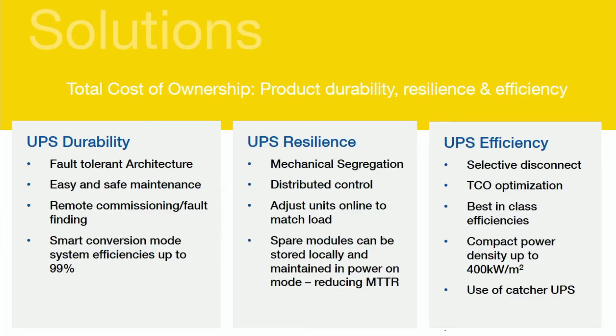Yeah, so this is where instead of having an N+1 type UPS application in each data hall, you would have one UPS in each data hall with one catcher UPS as the master redundancy, which would be connected via an STS network, obviously reducing not only your CapEx, but also your ongoing OpEx costs.